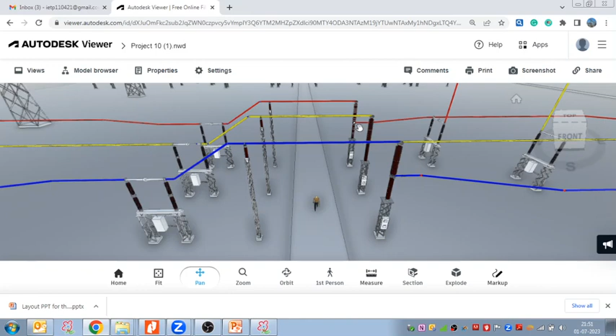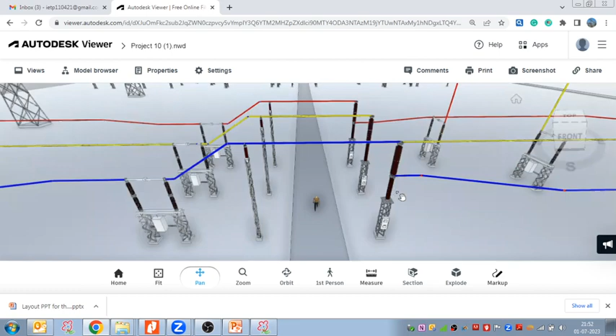Below 132 kV, the breaker can be handled manually, so that route would not be required. But above 132 kV, the breaker size and weight increase so much that it cannot be handled safely with manpower; we use an erection machine or crane to handle the circuit breaker. Due to that reason, again we have to plan a road near the circuit breaker.